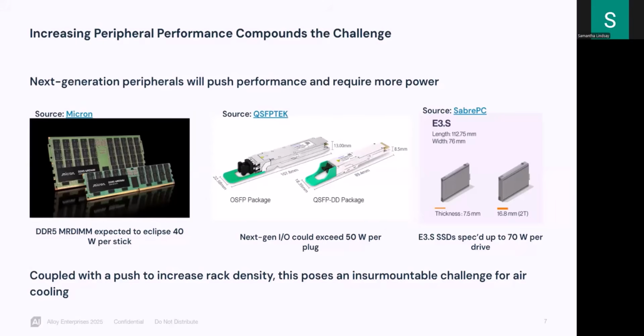Similar with input/output -- QSFPs, OSFPs. We're seeing estimates of next-gen systems with 50 watts per plug, compared to a fifth of that today. So again, a huge heat load issue there, and these are oftentimes in industry standard cages as well, so you have a limited amount of space to even put a liquid cooling solution into.